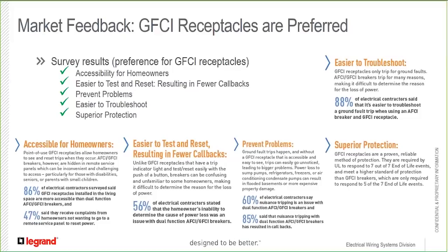Another reason why GFCI receptacles were preferred by those in the study is the ability to prevent problems. A ground fault trip can happen, and without a GFCI receptacle that is accessible and easy to see, trips can easily go unnoticed. This can lead to power loss, and this can compromise sump pumps, refrigerators, freezers, and air conditioning condensate pumps, which can result in flooded basements or even more expensive property damage. And with that, 60% of electrical contractors say that nuisance tripping is an issue with dual function AFCI, GFCI circuit breakers. And 85% said that nuisance tripping with dual function AFCI, GFCI breakers has resulted in a callback for them.